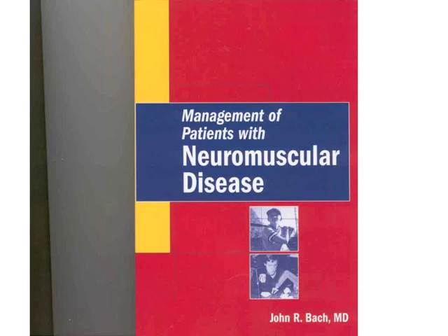So for people who want to air stack, they cannot use pressure cycling on any machine, whether it be BiPAP or a Trilogy or anything else. So we always prefer volume cycling so that patients can air stack, so that they can cough better and keep their lungs healthier.